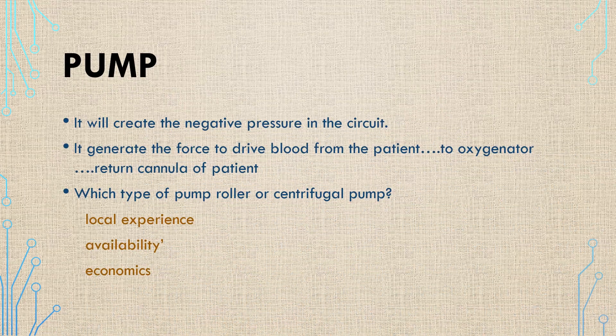The pump works by creating negative pressure in the circuit, which generates the force driving blood from the patient through the oxygenator and back to the patient. The type of pump used — roller pump or centrifugal pump — depends on local experience, availability, and economics.